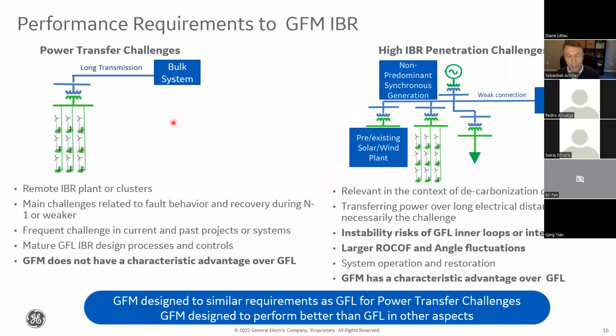Because there is not a characteristic advantage of grid forming in this case. Now, when you look at the problem on the right, it's very different. With the problem on the right, you have a system where you expect large angle fluctuations because you don't have significant synchronous machines close to these loads and inverter-based resources. Or, if the complete interconnected system has these characteristics, you would expect a significant rate of change of frequency, unless your inverter-based resources have grid forming features. So grid forming has a characteristic advantage over grid following for this type of problem: minimizing angle fluctuations, pushing back on the rate of change of frequency, and also, if the short circuit ratio gets really low, let's say 0.3, 0.4, 0.5, grid forming will be able to avoid some instability risks that you see in grid following inner loops or interactions at extremely low short circuit ratios.